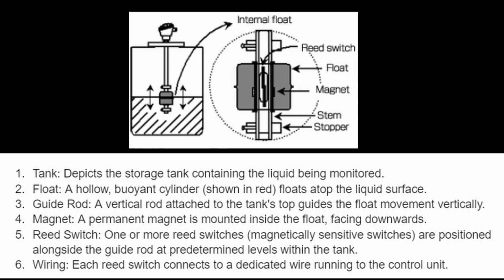1. Tank depicts the storage tank containing the liquid being monitored. 2. Float. A hollow, buoyant cylinder, shown in red, floats atop the liquid surface. 3. Guide rod. A vertical rod attached to the tank's top guides the float movement vertically. 4. Magnet. A permanent magnet is mounted inside the float, facing downwards. 5. Reed switch. One or more reed switches, magnetically sensitive switches, are positioned along the guide rod at predetermined levels within the tank. 6. Wiring. Each reed switch connects to a dedicated wire running to the control unit.